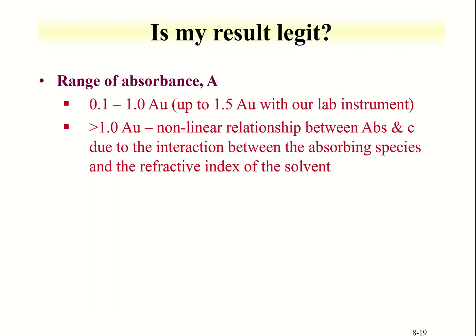Please make sure that the absorbance reading is within the tolerance as shown. It is not meaningful to obtain an absorbance reading beyond 1.5 AU as the absorbance is a logarithm scale of the ratio between transmitted light and reference light. An absorbance reading of 2 means that you have almost 100% absorption. At this reading, it means that your sample is absorbing most of the light and would be too dark for an accurate measurement to be made.